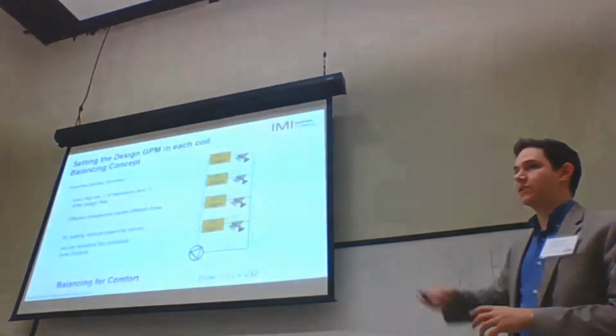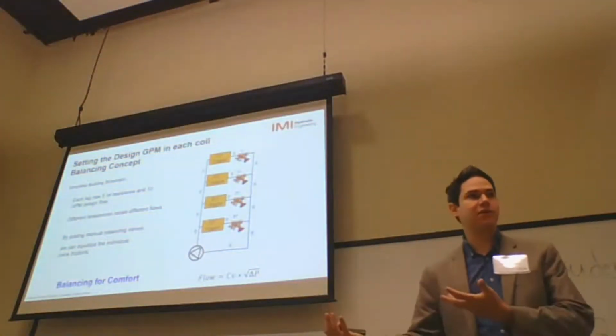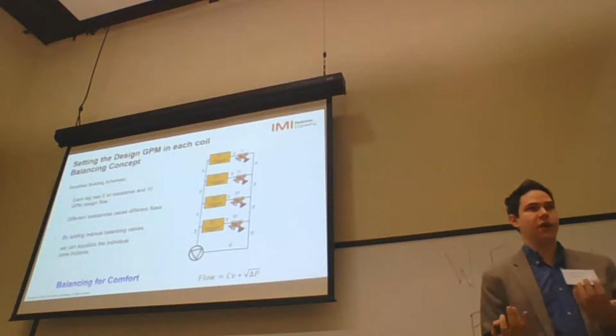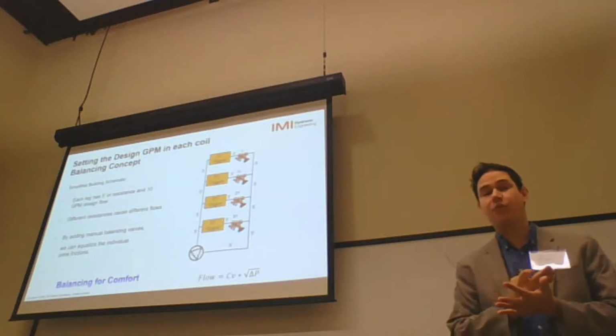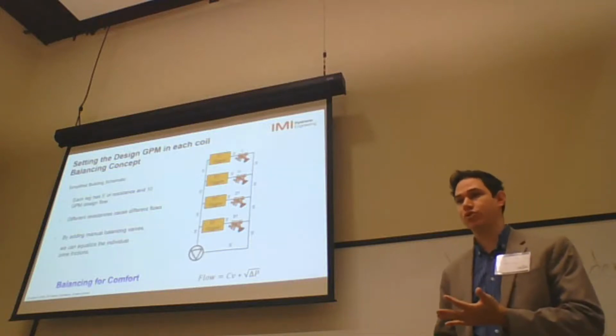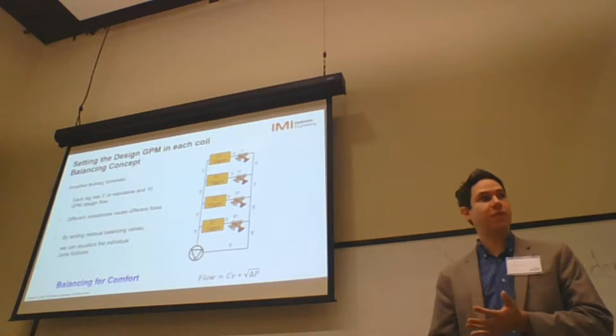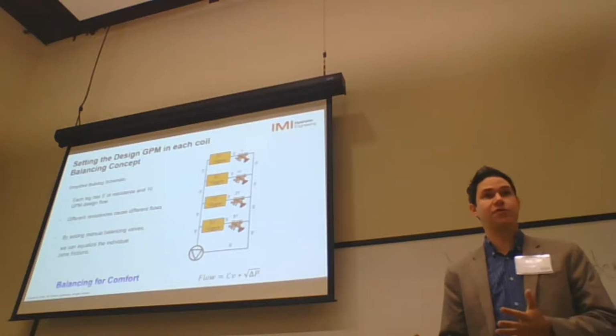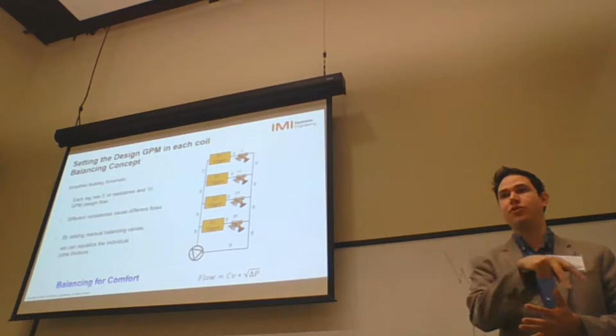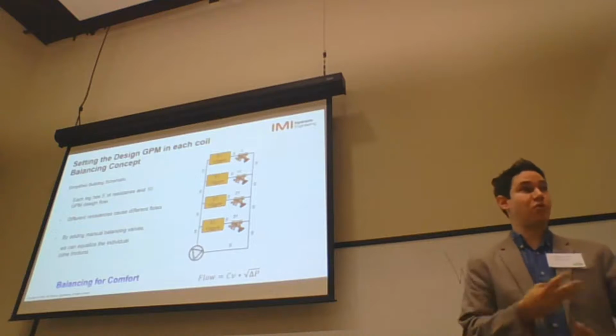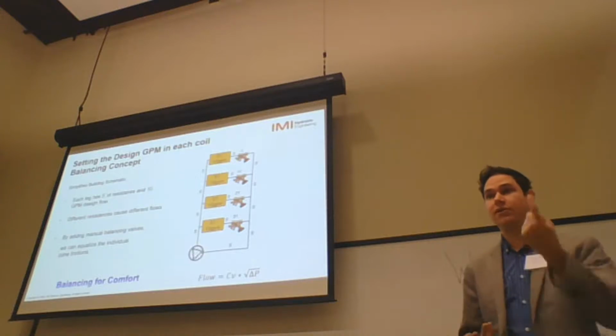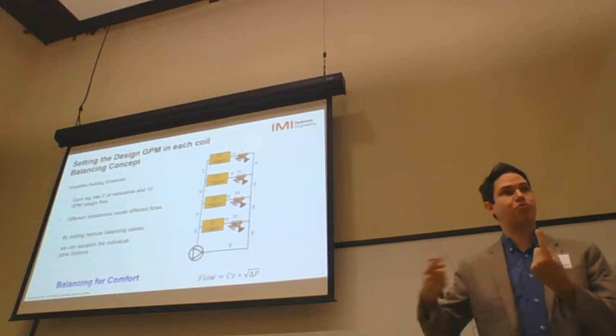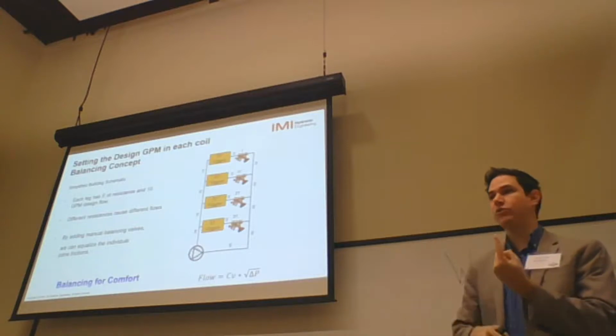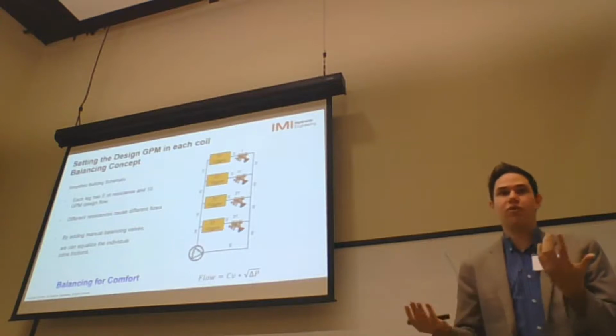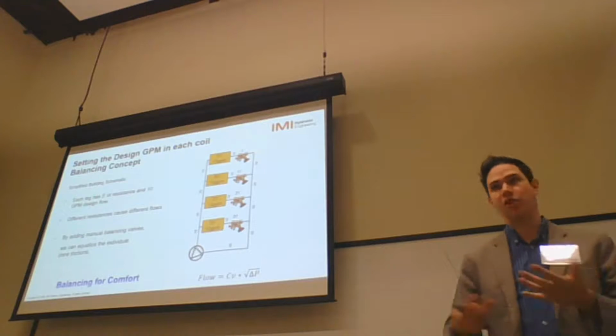The reason I'm keeping 1 foot in my last coil is that manual balancing valves do not have a requirement of minimum pressure drop. What is the requirement for a minimum pressure drop? It comes from the DP sensor that you are using to measure on the valve. Most of the DP sensors on the market require around 1 foot as a minimum pressure drop. If you have less than that, you have lower accuracy in your measurement, which is not recommended.